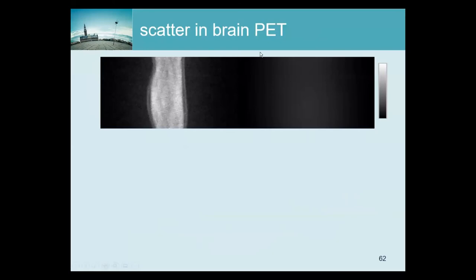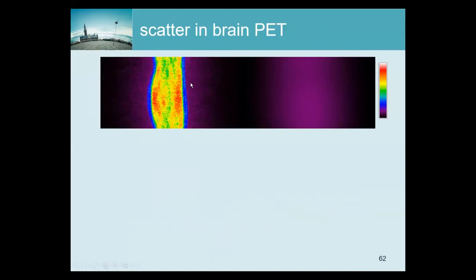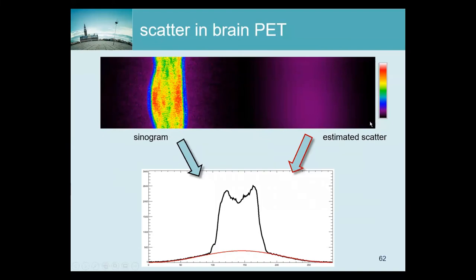For a brain scan you can nicely see the scatter tails, because this is the forward projection of the activity in the head, and here these LORs do not go through the patient, so they should not have seen any activity. This is the measured sinogram, and this is the estimated scatter sinogram. Here you see some profiles, and you can see that the scatter explains why there is activity outside the patient. For the brain, the scatter is not too bad, although it's still close to almost 20 percent.